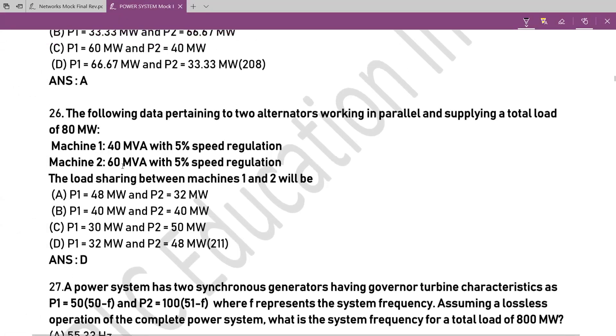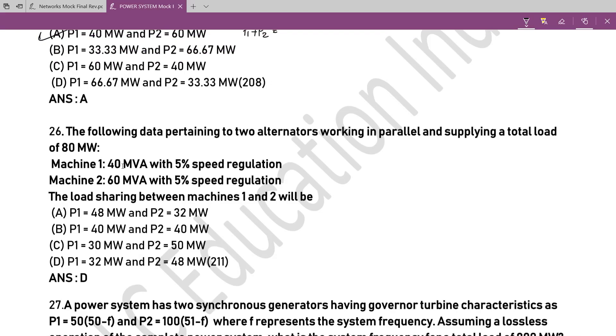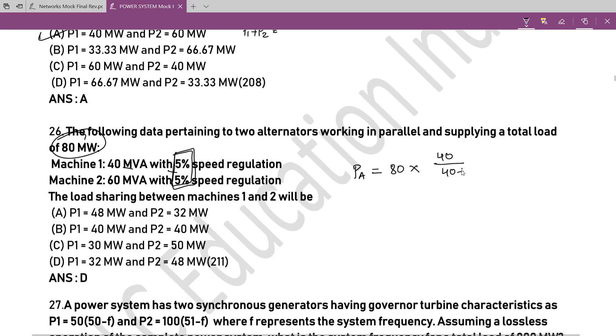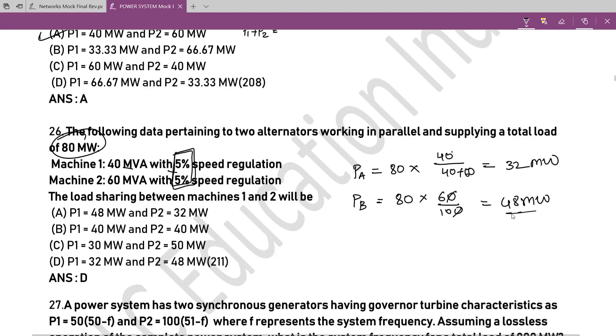Question 26: Two alternators are working in parallel supplying a total load of 80 MW. Machine ratings are 40 MVA and 60 MVA, with the same speed regulation. When speed regulation is the same, load is shared in proportion to capacity. Load shared by generator A = 80 × 40 / (40 + 60) = 32 MW. Load shared by generator B = 80 × 60 / 100 = 48 MW. Option D is the answer.